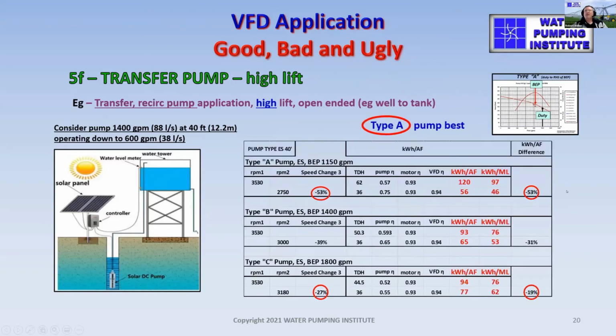So in summary now, a type A pump, if we just look at the speed change alone, we will show a 53% saving. And this is what the VFD people will tell you: change the speed, it'll yield the cube of the speed change. Well, that's 53%. Now, in this particular case, I've calculated the actual energy savings, and it is actually 53% because it started off at the same pump efficiency as it's finished up.